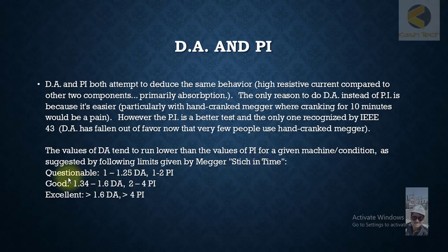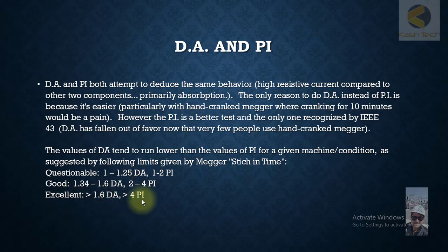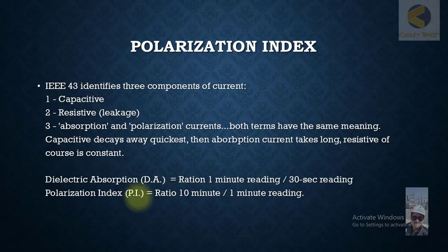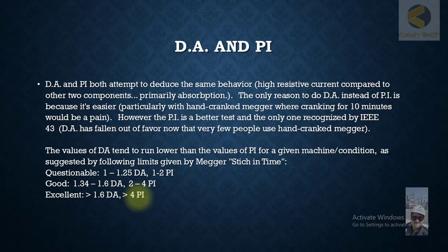If you are getting a DA ratio between 1 to 1.25, or PI between 1 and 2, then it's questionable insulation and you have to check it — it might not be good. If the DA value is between 1.34 to 1.6, or PI is between 2 to 4, then it's okay. If DA is above 1.6 or PI is greater than 4, then it's excellent. Thank you very much.